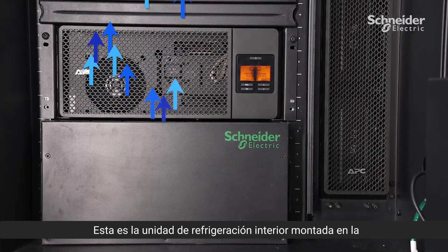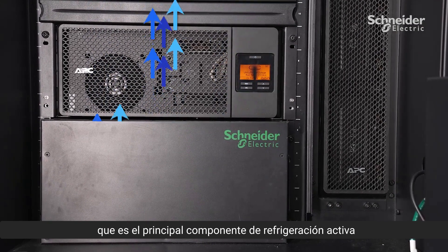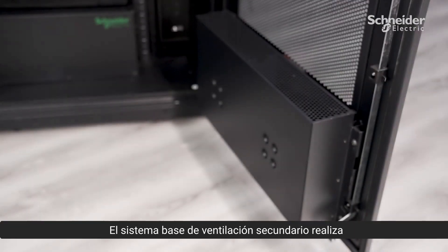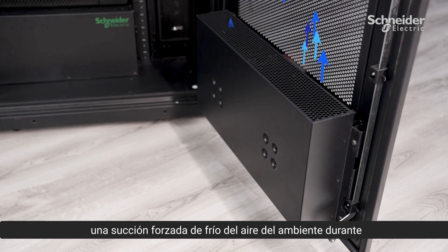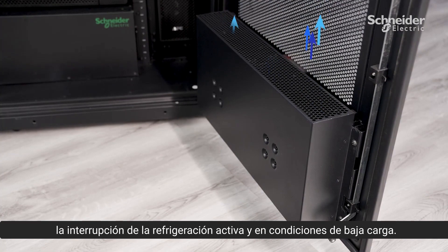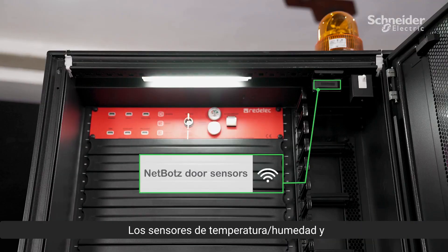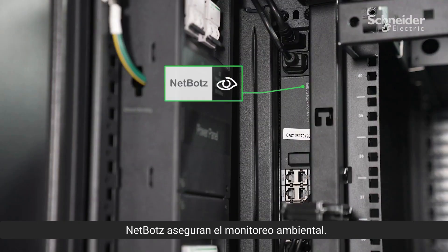This is the indoor cooling unit mounted at the bottom to provide cold air for the IT equipment, which is the primary active cooling component. The secondary fan-based system performs forced ambient air cooling suction during active cooling interruption and in low-load conditions. Temperature, humidity, and door sensors integrated with NetBotz ensure environmental monitoring.